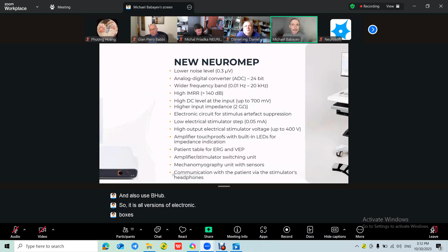Now let's speak about the advantages, the benefits of the new devices, and I will compare this new device with the previous, existing version NeuroMep 4. This new one has a lower noise level, 0.3 microvolts. Maybe you remember that the existing device has 0.4 microvolts. The analog digital converter, ADC, is now 24-bit. The previous one has 16-bit only. The new device has a wider frequency band, up to 20 kHz, and a higher CMRR, common mode rejection ratio. Now it is more than 140 decibel, and this parameter is very important to know how well the device can decrease interference noise from other power supplies.